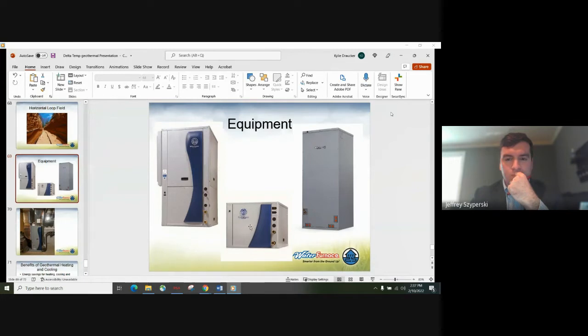This system next to it is a pair system, a split system. This would be the compressor portion, and this would be the air handler portion. A lot of times these are installed where we're not running water lines through the house. We might keep the compressor section on the lower floor and put the air handler on the upper floor. It may also depend on an existing home. If we're retrofitting a geothermal system, this type of system might work better. Of course, there's a line set between them connecting them.